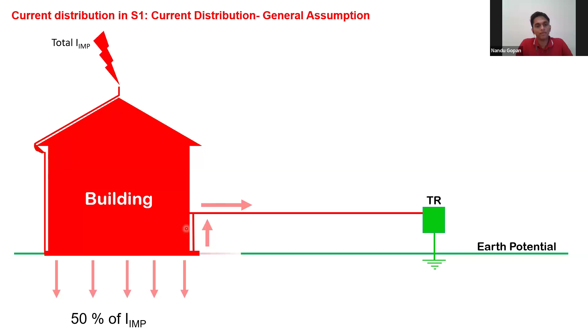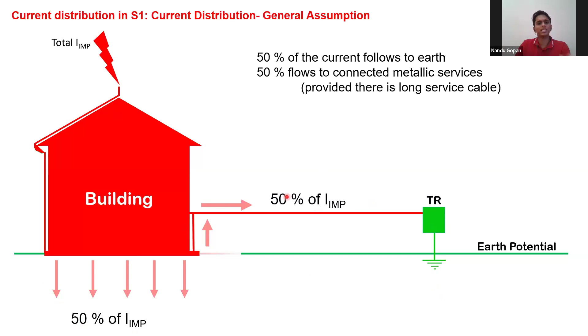Before that, let me explain something called current distribution. It is a general assumption that if there is a lightning strike to your building, 50% will go to the soil, and 50% will travel through the power lines back to the soil again. They just take an assumption of 50%. Generally this won't exactly be the case. Sometimes if you have done a very good number of bondings, it will be 90% to the soil and 10% through the lines. It depends, it can vary, but generally you can take this 50% assumption.